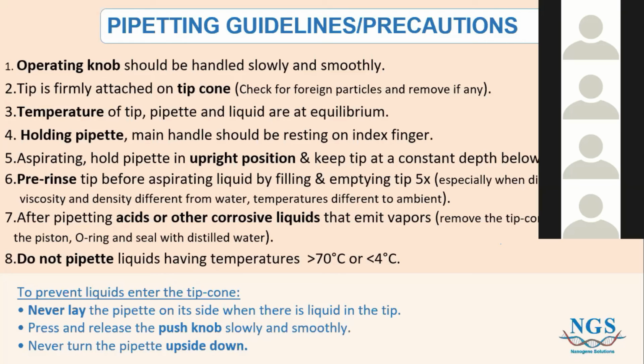No, I would say always go with 10 readings, right? So for every testing volume that you're using, use 10 readings. So you need to do it 10 times. You want to aspirate it, dispense it onto the weighing balance, and then read it, and then do that 10 times. So you get 10 readings. 5 readings can be a little bit too little, so to be on the safe side, I would suggest going for 10 readings.